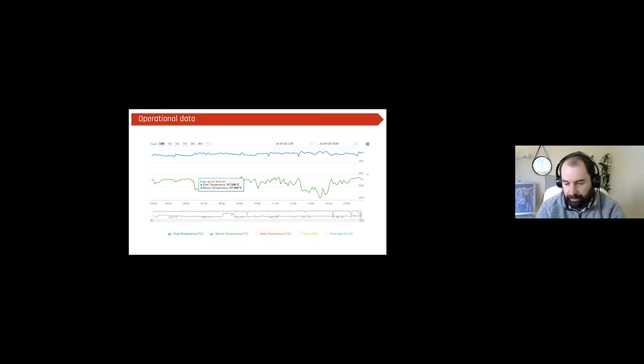So when would we use fifth generation heating, district heating, within buildings? I have a couple of quotes, a couple of sources. There's one rough metric that fifth generation district heating could be appropriate if more than 40% of the load must be cooling. Also, Phil Jones from Building Energy Solutions suggests a figure of around 50%. So if 50% of your total load is cooling, then fifth generation could be a viable technology.